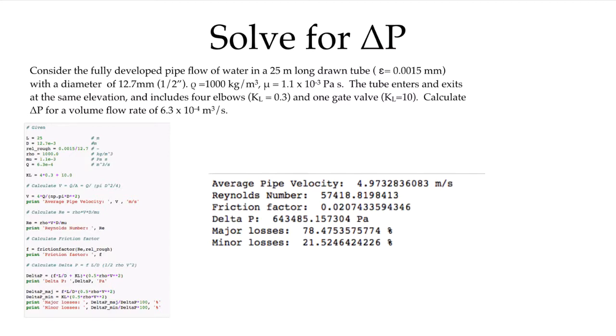We can see that in this example, almost 78.5% of the losses are due to the friction in the straight sections of the pipe, while 21.5% are due to the minor losses. So there's an example where we have a known flow rate and we calculate the pressure drop.